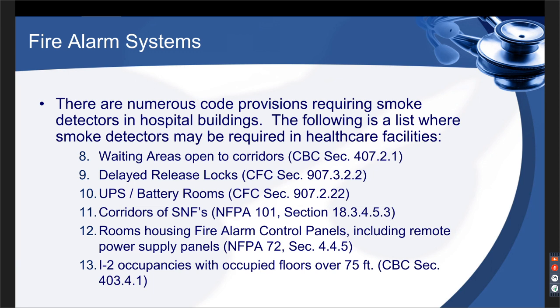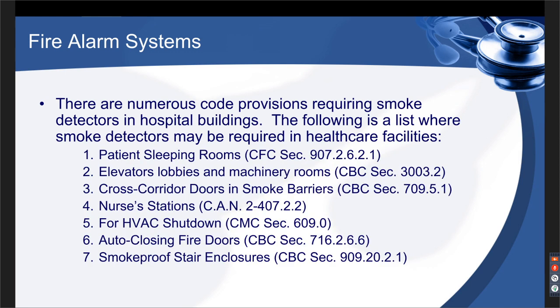So the slide says there are numerous code provisions requiring smoke detectors in hospital buildings. I should have worded that differently, because some of these would be required regardless of whether it was a hospital building or not. For instance, if you have a room housing a fire alarm control panel, regardless of the occupancy type and the building type, NFPA 72 would require a smoke detector in that room. And as mentioned earlier, if you have an elevator lobby and a machine room that requires elevator recall, then a smoke detector would be required by section 3003, regardless of the building or occupancy type. So I understand the question now. Sorry for the confusion. Again, if the person wants better clarification, send an email to the regs unit at hcai.ca.gov.